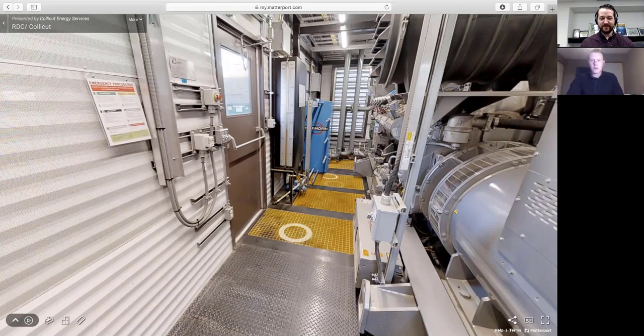And here, this is the plate and frame heat exchanger. I'll zoom in here in a second, but what's happening is that consolidated heat from the jacket water and the exhaust comes into this heat exchanger, and this is where the heat is transferred from the CHP loop in this facility through to the intermediate loop.